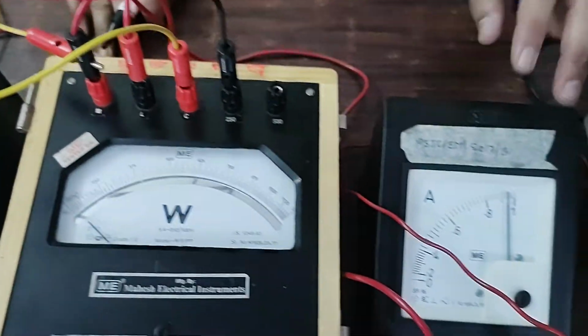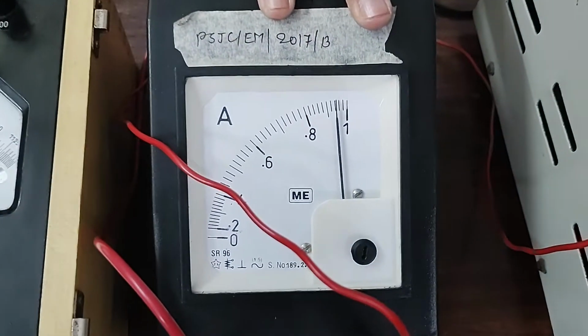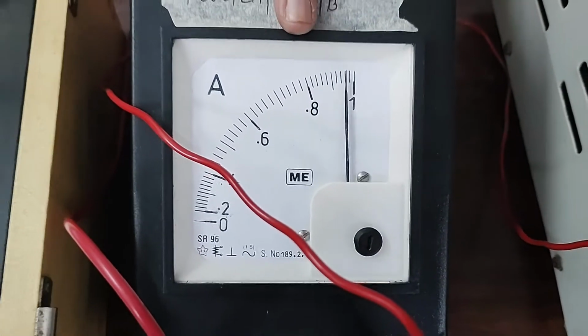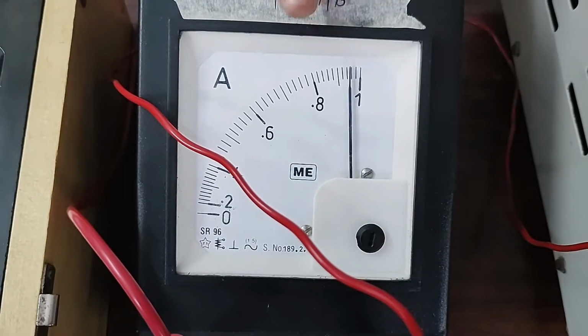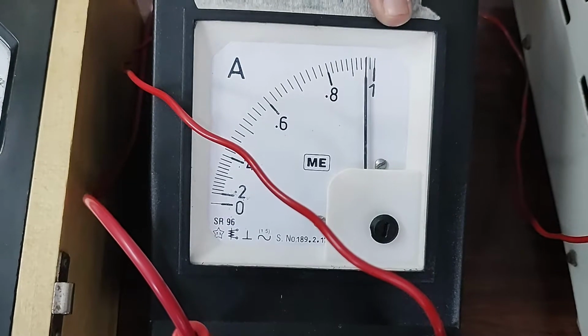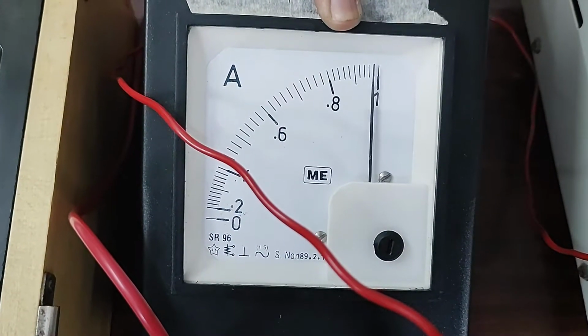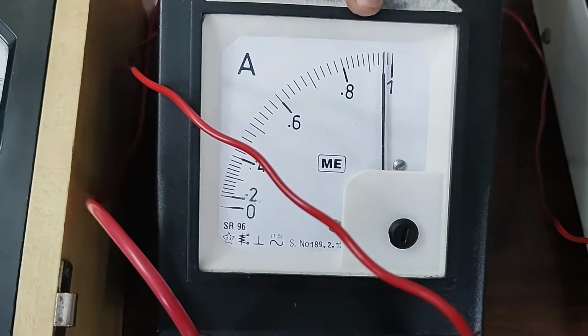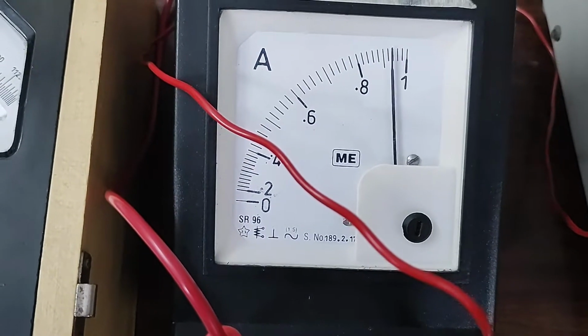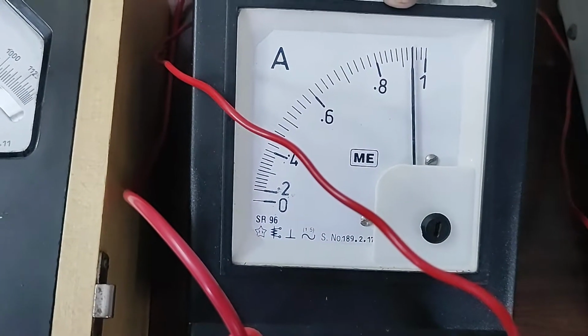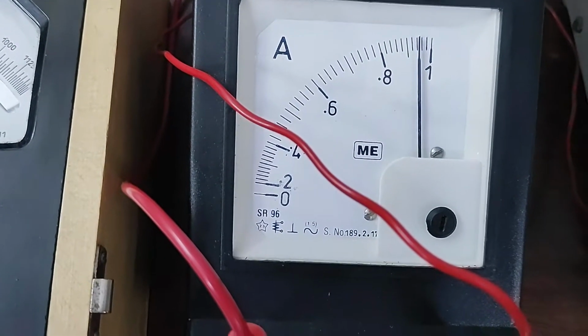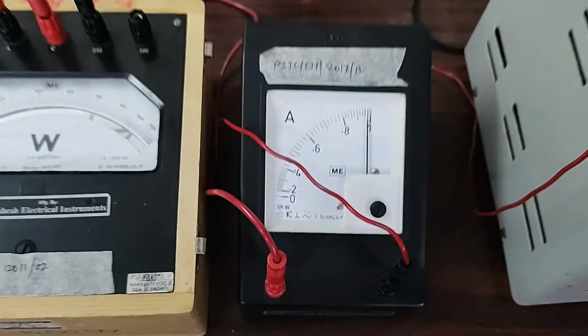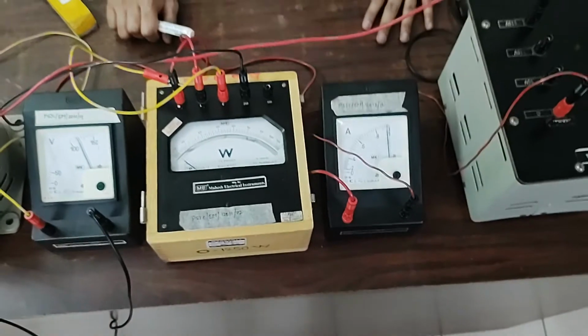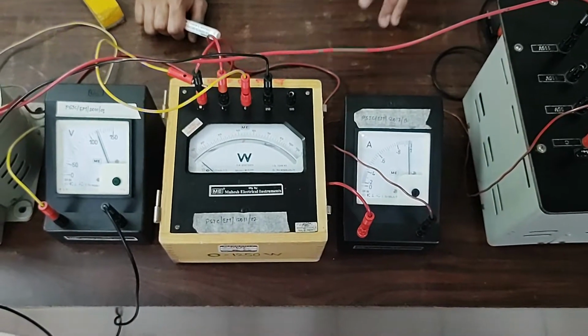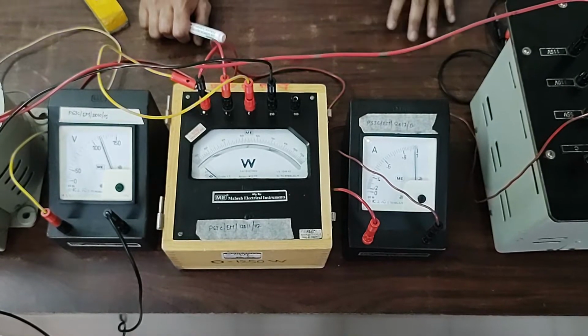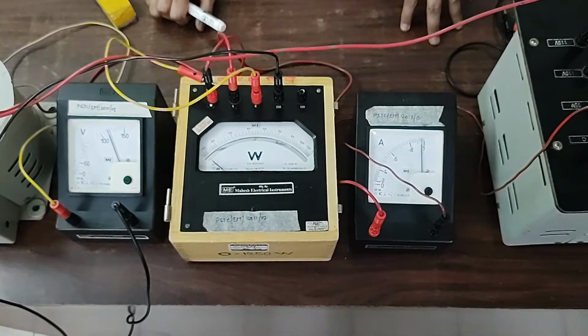At the same time, our ammeter is also indicating the current magnitude. For the ammeter, we can see that it is indicating between 0.8 and 1, and there is one bigger line between 0.8 and 1 which is 0.9. Each small line is indicating 0.02 ampere. So the reading of the ammeter here will be 0.94 ampere. This is the current which the transformer is taking in open circuit condition to supply the core losses and magnetize the core. So let us note down this reading and the observation and move on to the conclusion.